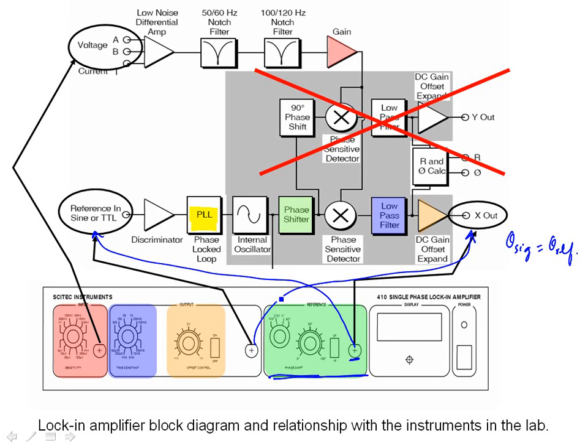So, what we have is essentially the input, which goes here, and the line frequency filters, or notch filters, at the line frequency and twice the line frequency, to take care of the line noise. And so, the input and the reference are multiplied, as we've seen earlier, and then pass through a low-pass filter. So, this is basically the PSD mathematical thing that we have seen earlier.